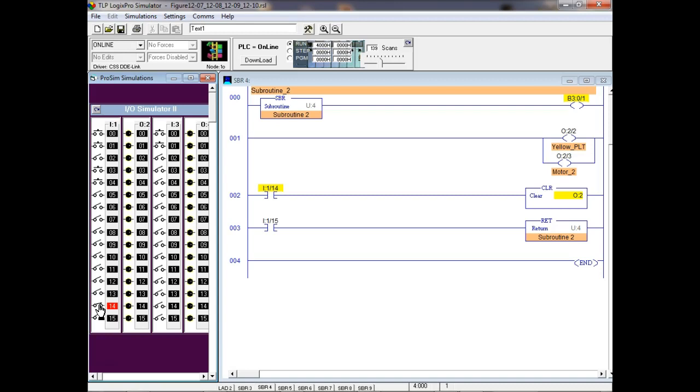Now, unconditional subroutines update instantly. They look like they're part of the ladder. A lot of programs, like the one that runs the robot, use subroutines that are not unconditional. Those are just written to split the program up into individual modules. But we can make them conditional. You'll find that too. But you have to remember, and it makes sense, that if the subroutine is not running, then all your outputs are going to stay the way they were, right? Y'all understand that?